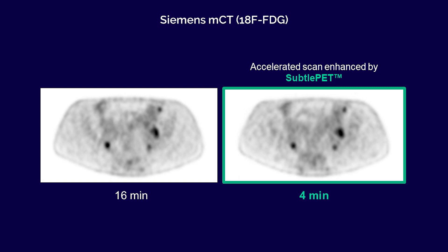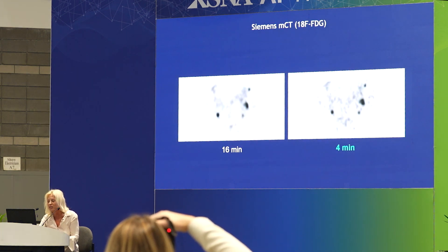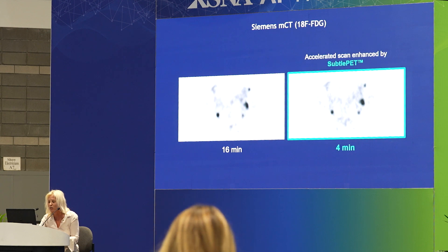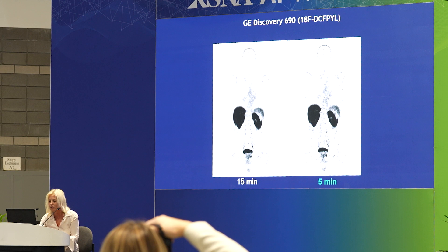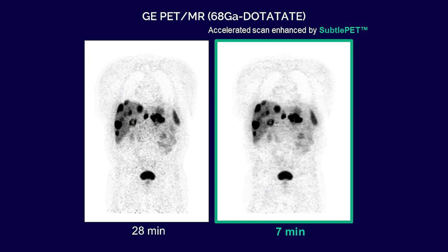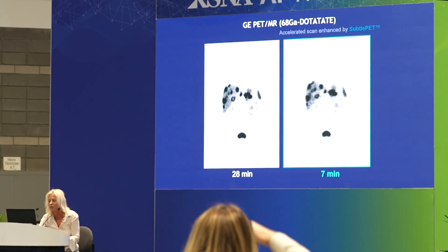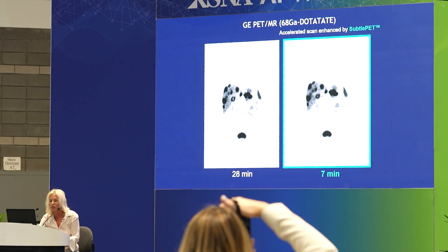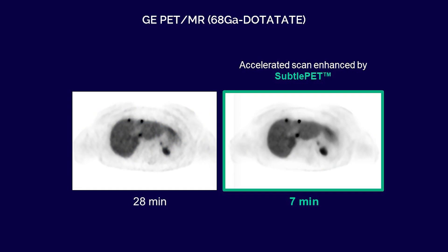Here are different examples of PET using different radiotracers and different vendors. The original scan on the left took 16 minutes — alter the protocol to get down to four minutes and then restore the image quality with deep learning. Here's another whole body PET that took 15 minutes, altered to five minutes, transformed by deep learning enhancement to restore image quality. Here's a patient with a lot of metastases — this exam took 28 minutes, altered to seven minutes, and then we restore the quality with deep learning. You can see in the contrast to noise ratio those lesions become very conspicuous.